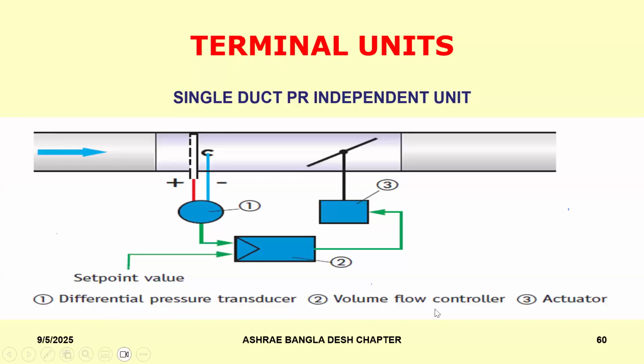Just to give you an example, let's say that there is about 500 CFM of air going through this duct, and that's being measured. And then let's say the set point is based on CO2 sensing. And we have said that, look, if you want to maintain a set point of 800 ppm, which is acceptable within the space, we need about 500 CFM. Let's say that in that space, the occupancy levels have gone up, the CO2 level has gone up, and it has gone to, let's say, 1000 ppm or 1200 ppm. At that point in time, this controller will give a feedback to this actuator here, which will allow this damper to open up to increase the ventilation. And it will open it up to the extent required to bring the CO2 levels back to the set point value. So this set point could be either CO2, or VOC, or temperature, whatever. So these are the kind of devices that you can think of using.